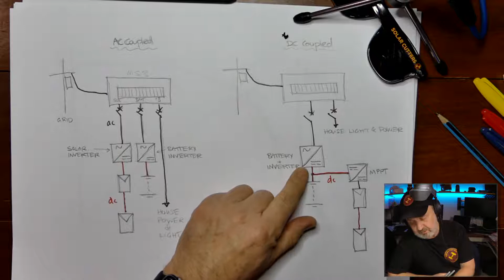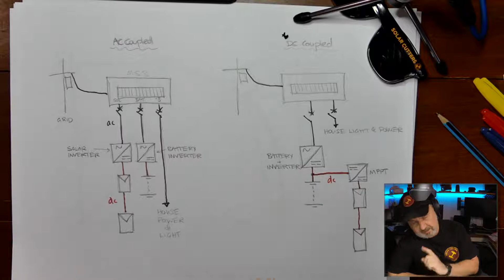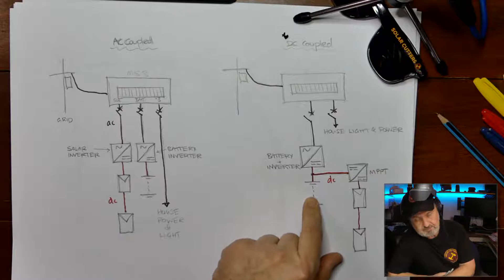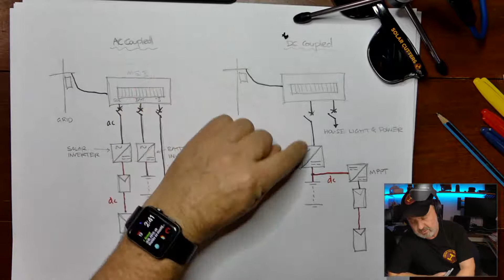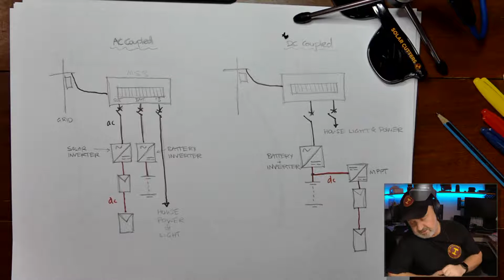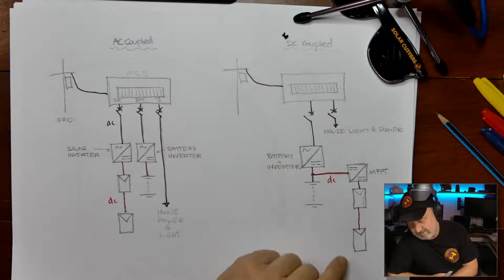So only one inverter. The DC side is a separate design, but, and this is where Peter will probably reinforce it, you've now got a dedicated way of charging that battery. It's independent of whatever happens on the AC side. You can take away the grid, you can take away the battery inverter, you'll still charge that battery. So it's got one dedicated purpose, which is to provide clean, smooth DC power to charge that battery.